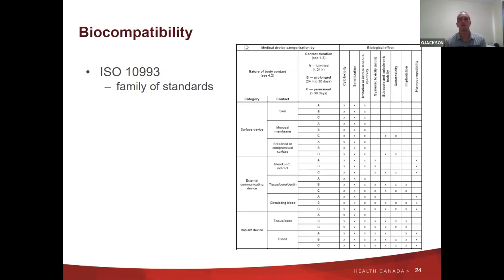So ISO 10993 is the typical family of standards. And it lays out, based on contact duration and based on how it contacts, what tests are required. So we see in my group a lot of skin contact for limited duration. Then basic testing includes cytotoxicity and skin irritation kind of testing.